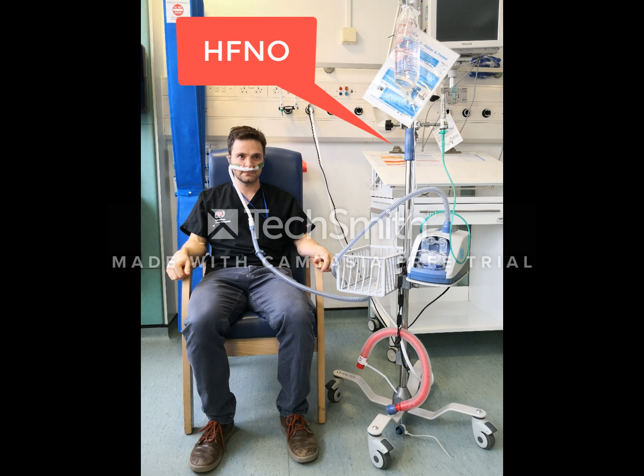This device is high-flow nasal oxygen, often referred to as HFNO. It delivers up to 60 litres of humidified gas per minute, and the fraction of oxygen delivered can be adjusted between room air to 100%. Part of its mechanism is through the washing out of respiratory tract dead space. This means that carbon dioxide can be controlled to some extent, as well as oxygenation.